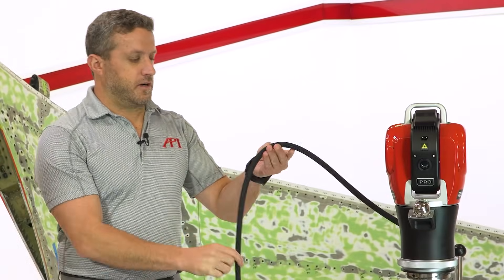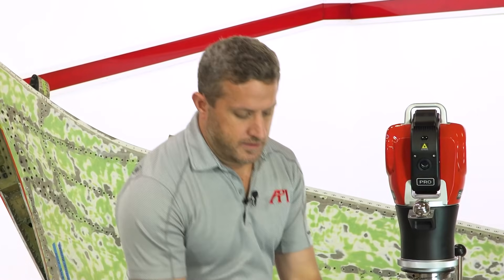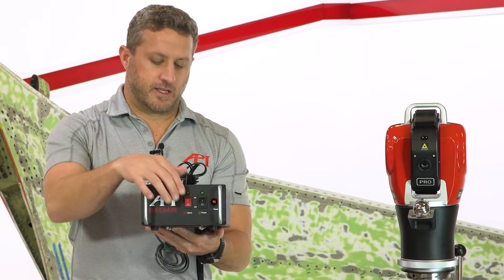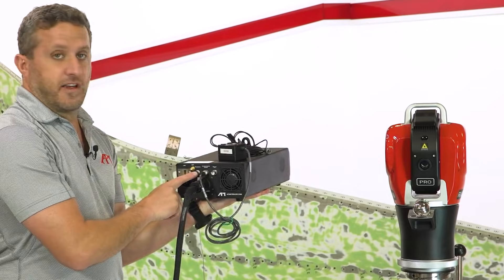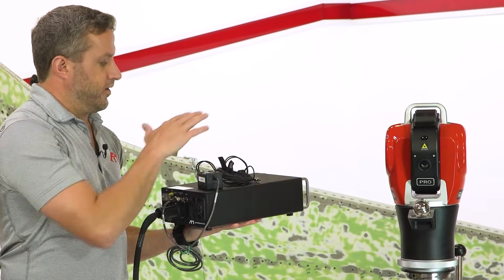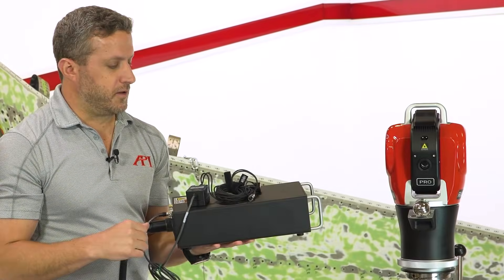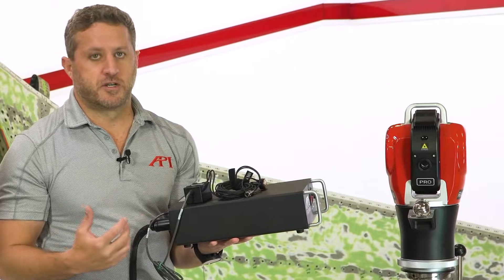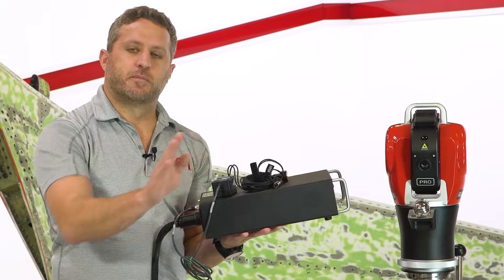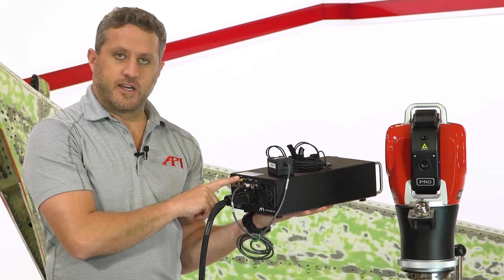It is connected through a very flexible cord that you can get at various lengths, and that goes to a control box where you power up the laser tracker, plug in any accessories, as well as a weather sensor. This weather sensor is meant to understand your environment — humidity, temperature, and pressure — so it can relate that information to the laser and tell it how to push the beam through the air. There are accessory ports on the back, and many of the accessories I'll go over will work with the Pro.